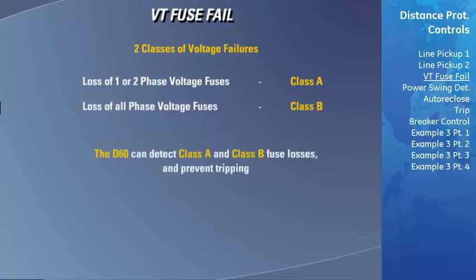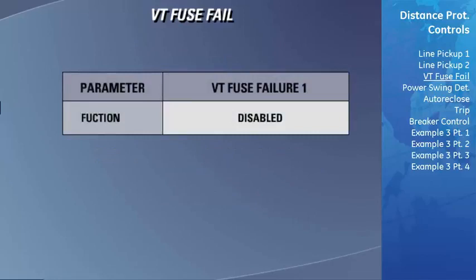The D60 has the ability of detecting both classes of fuse failure and can block the distance elements from tripping in both conditions. The FlexLogic operand that is output from the VT fuse fail logic is labeled Source X VT Fuse Fail Operate. The X after the source represents the number of the source that this VT fuse fail element is protecting. This operand will turn on whenever the D60 detects that one or more of the VT fuses has blown. There is only one setting that needs to be set if the VT fuse fail feature needs to be used. Simply enable the fuse fail feature for each source you require protected.